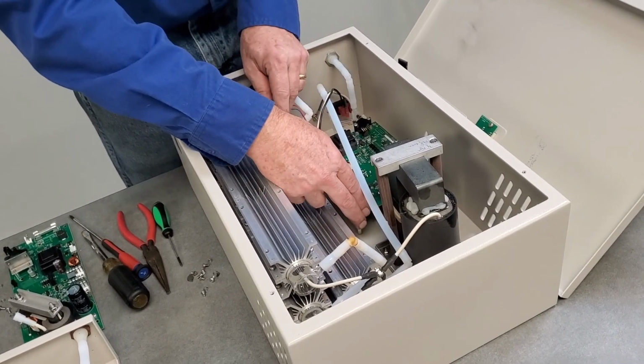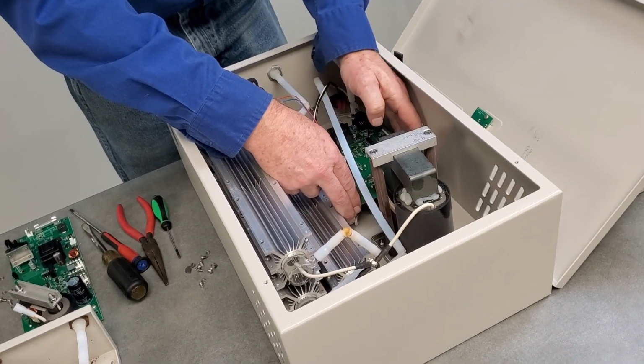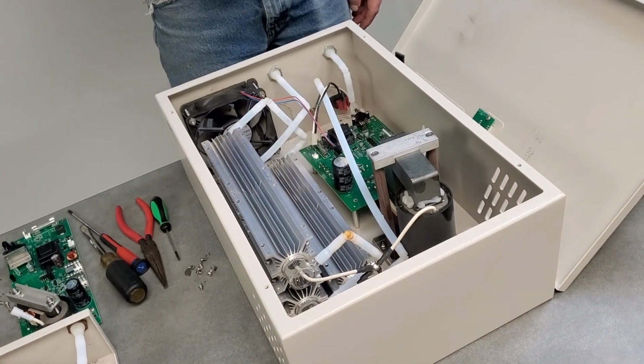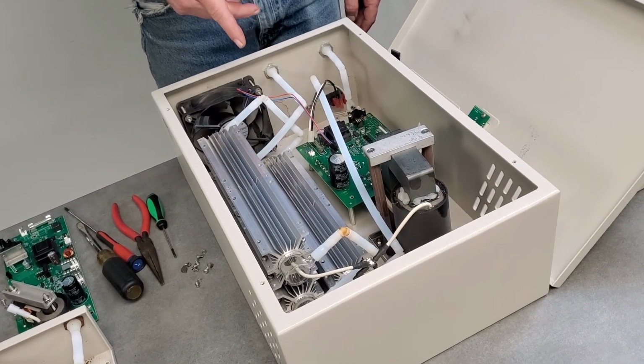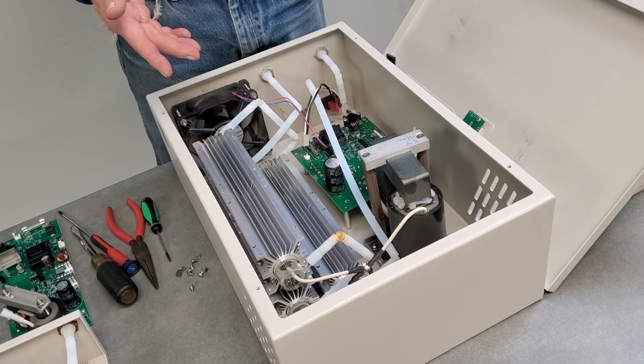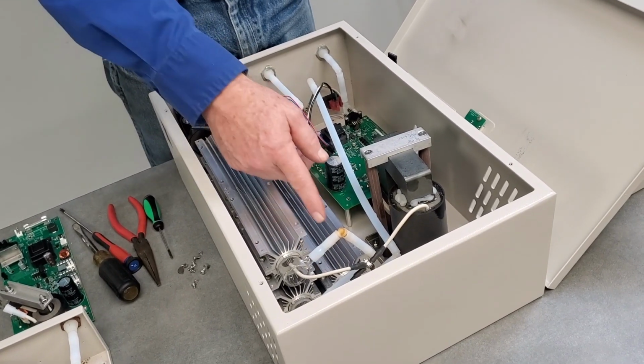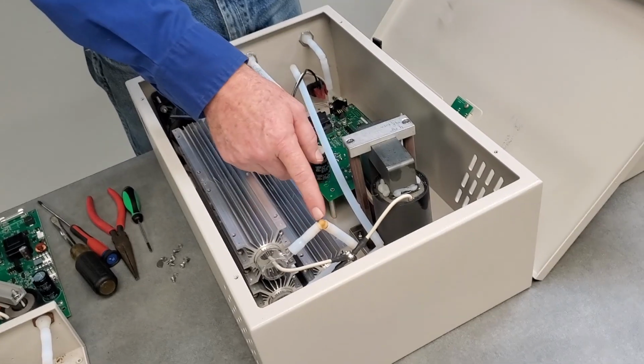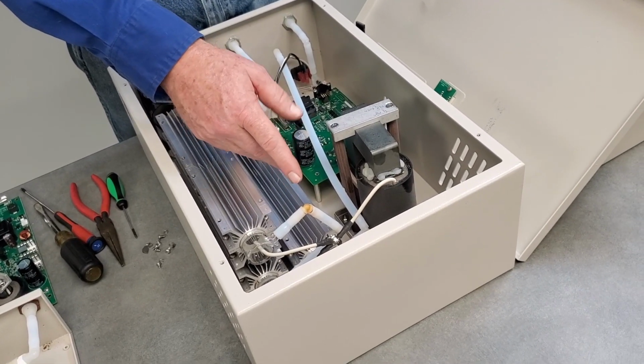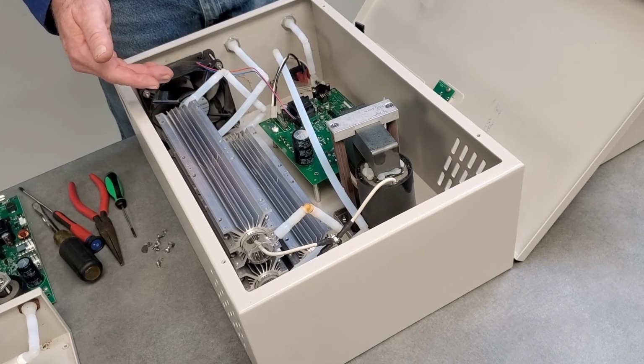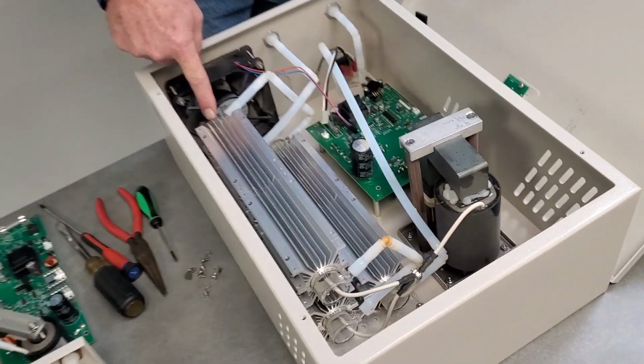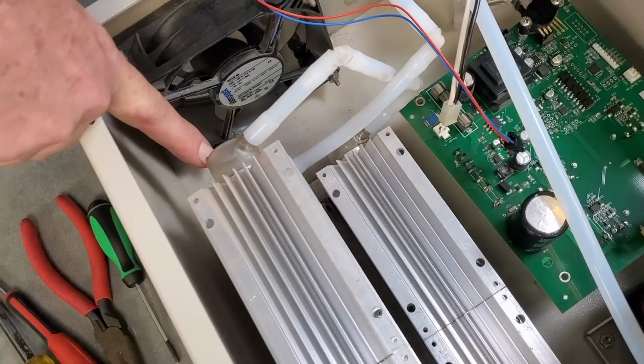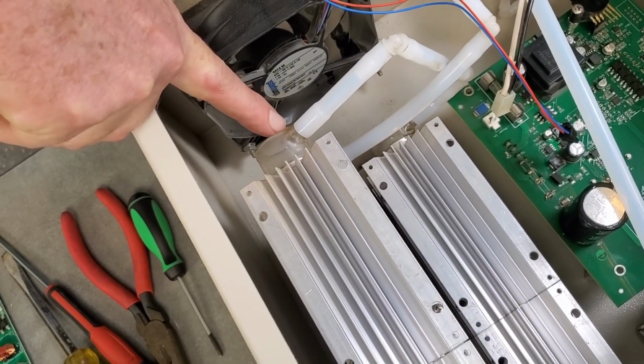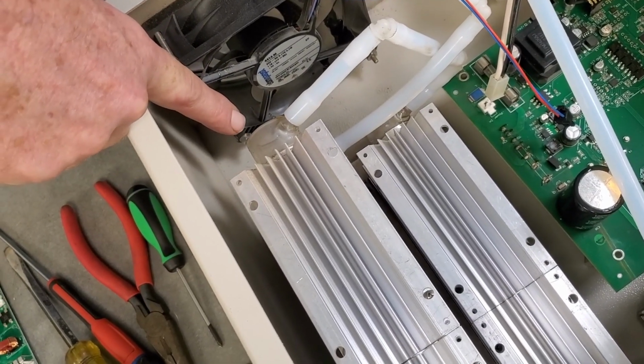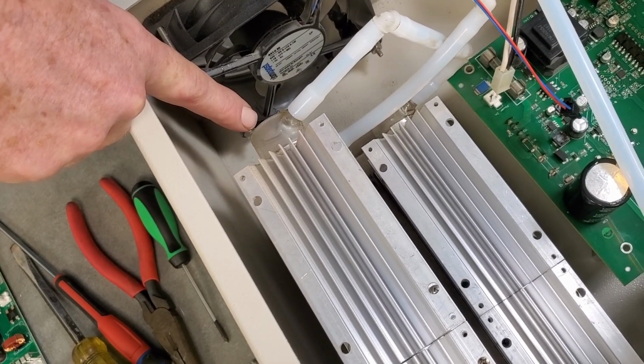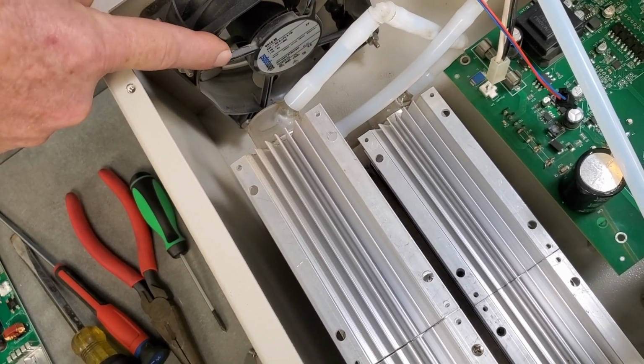Now, I've already determined that the circuit board in here is not working. One of the things that you can see that may have led to some of these failures: this brown coloring on these elbows indicates that there's been quite a bit of heat in the cabinet. And another thing, way down in here, you see these little plastic drips, which indicate that this got quite warm, and it's likely that this fan quit working.